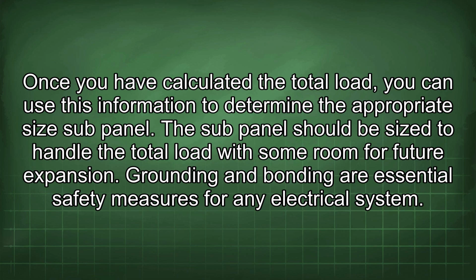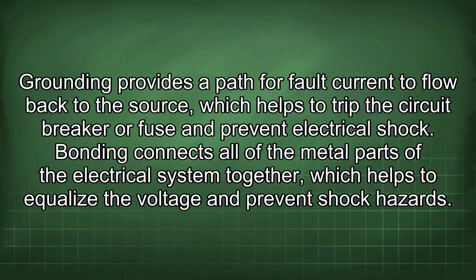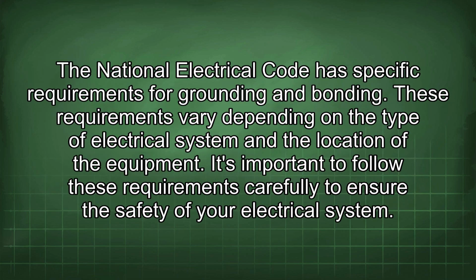Grounding and bonding are essential safety measures for any electrical system. Grounding provides a path for fault current to flow back to the source, which helps to trip the circuit breaker or fuse and prevent electrical shock. Bonding connects all of the metal parts of the electrical system together, which helps to equalize the voltage and prevent shock hazards. The National Electrical Code has specific requirements for grounding and bonding. These requirements vary depending on the type of electrical system and the location of the equipment. It's important to follow these requirements carefully to ensure the safety of your electrical system.